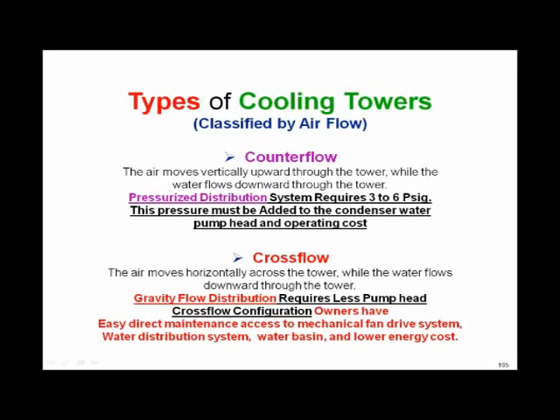Recognize that on counterflow towers, there is no hot water deck. There are spray nozzles, and those spray nozzles need 3 to 6 pounds of pressure to work. On a crossflow tower, you have hot water basins that flow by gravity. The message is the counterflow tower has to have 3 to 6 pounds more pressure on your condenser water pumps than crossflow. At 3 to 6 pounds of pressure, maybe 10 to 15 feet of pump head, don't come up short. You've got to do a detailed pump head loss calculation on your towers.